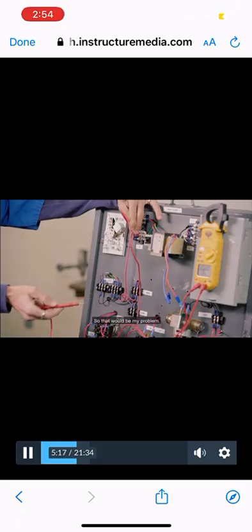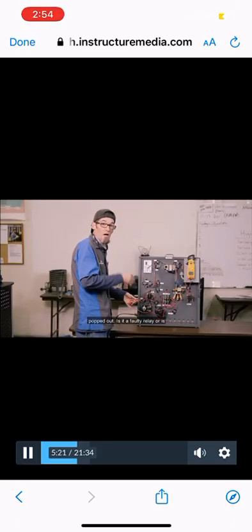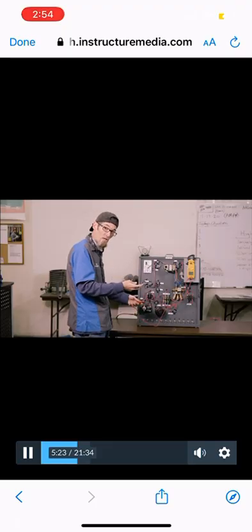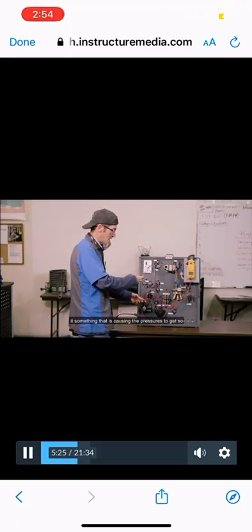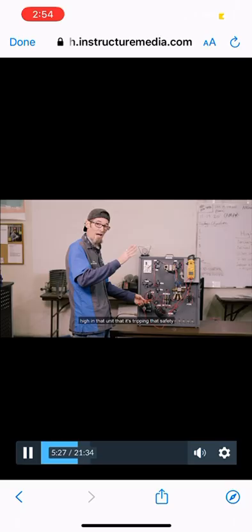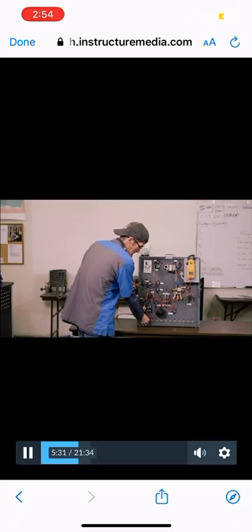So I'm going to look, and I actually don't have any voltage on there. What this tells me is that my high pressure switch is open. The voltage is going into it, but it's not coming out the other side. So that would be my problem. In the field, I would be finding out why this thing popped out. Is it a faulty relay, or is it something that is causing the pressures to get so high in that unit that it's tripping that safety device? Okay, so that would be switch number 2.